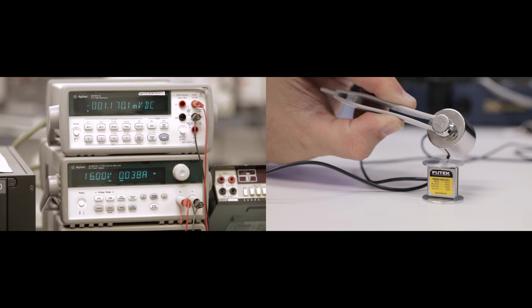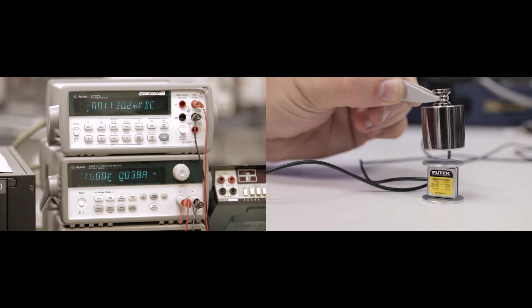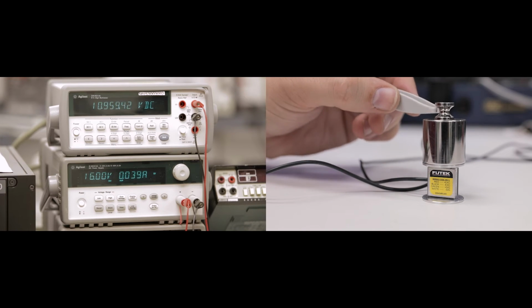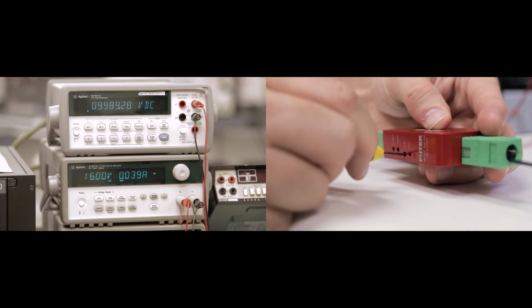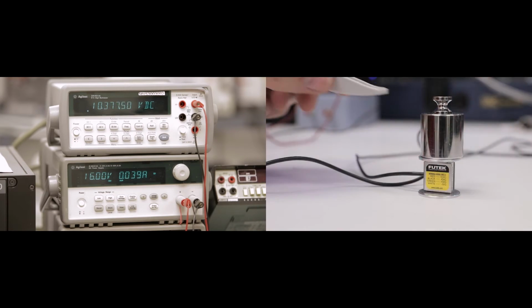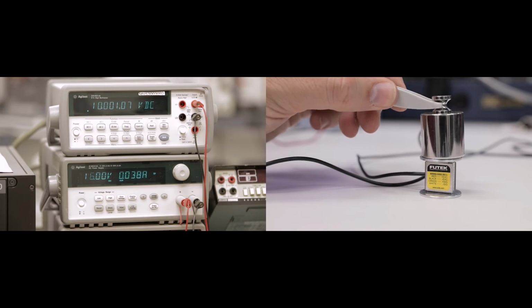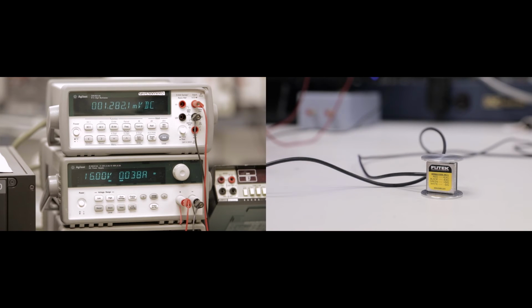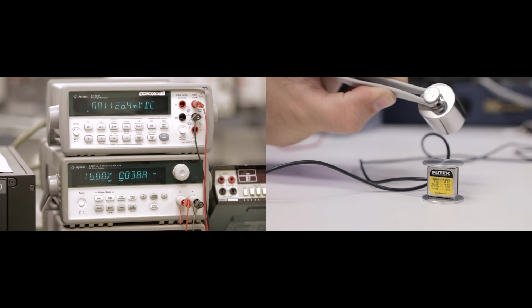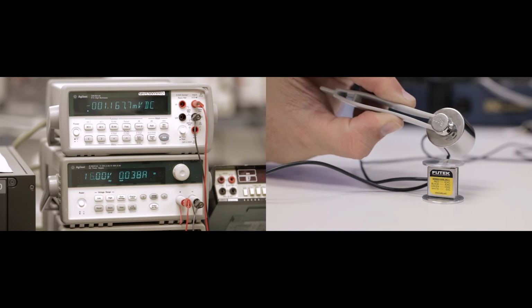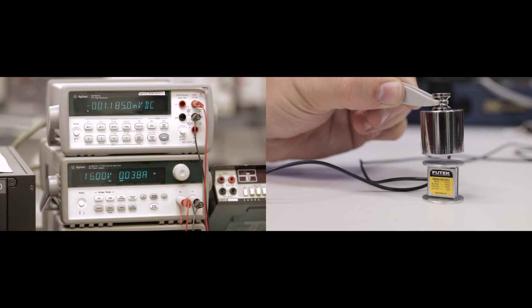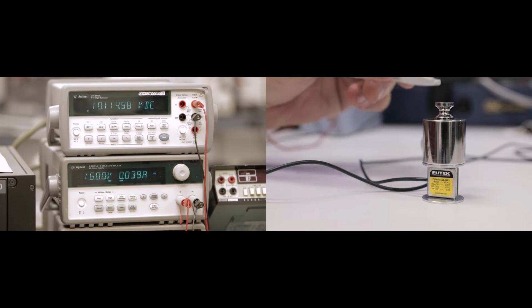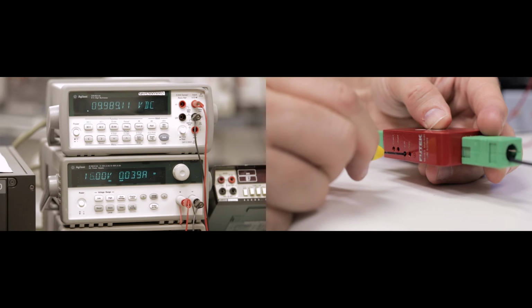Next, place the known load onto the sensor and adjust the output to as close to where it should be for the applied load using the span potentiometer. Remove the load and reconfirm the zero output, adjusting if necessary. Next, reapply the known load and reconfirm the output under load, adjusting if necessary. Repeat several times as needed until the zero and output under load are as close to where they should be as possible.